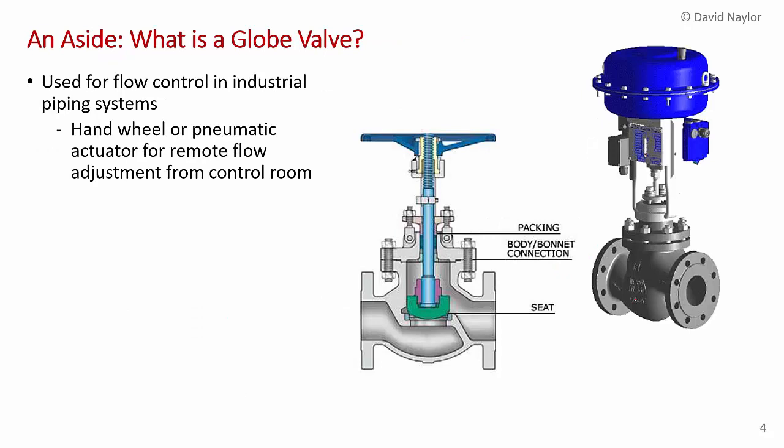As an aside, a globe valve is used for flow control in industrial piping systems. It can have a hand wheel to adjust the stem and seat position, or a pneumatic actuator for remote control from a control room. It has a round globular body, unlike a gate valve which is used for completely shutting off flow.